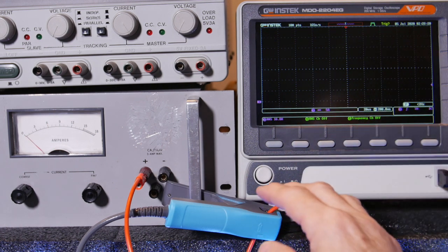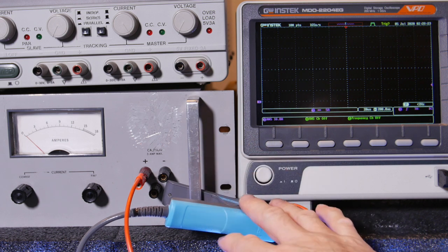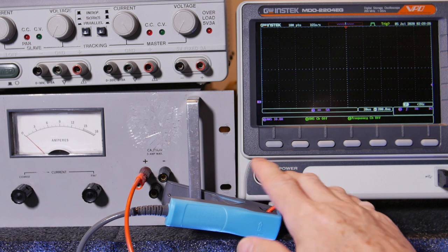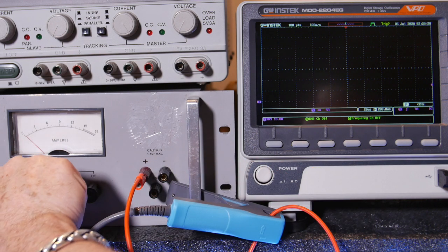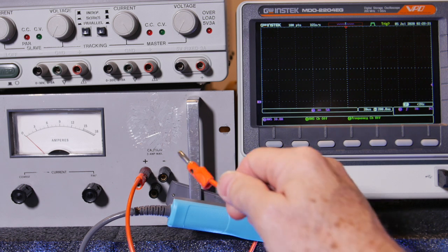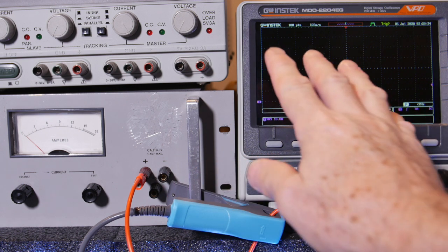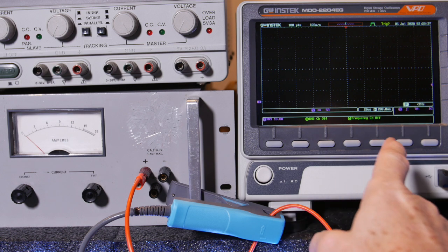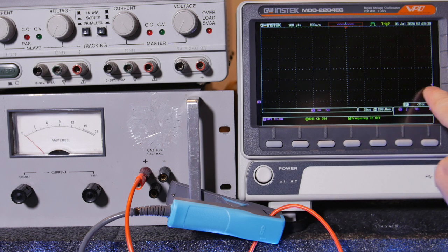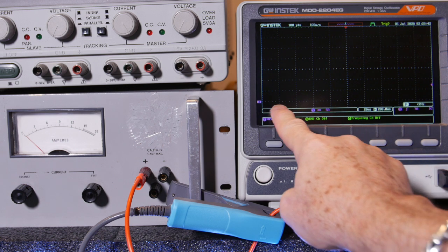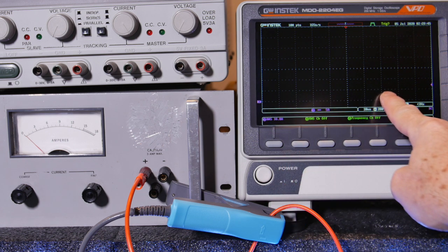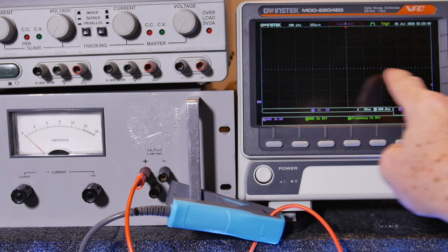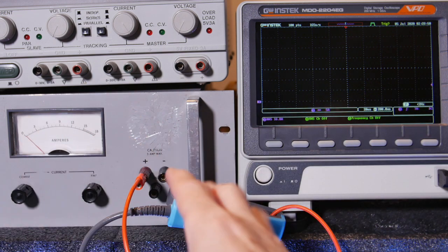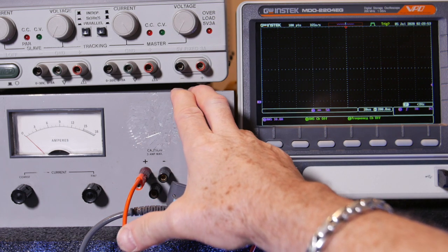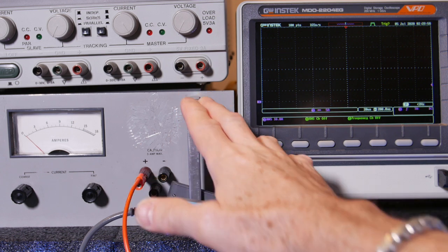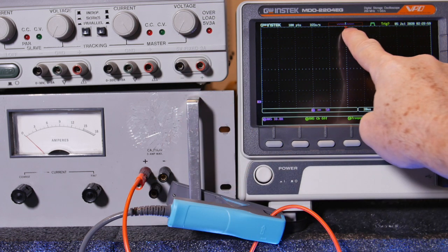Alright, we're going to go to a low current setting in a moment. But while we're set up on our 100 amp scale, let's try a surge current, okay? So what I'm doing is I've maxed this guy out, and we're going to just poke this in here. But what I have to do is go over to my scope and hit single trigger, okay? And then I'm going to see my triggers right here. By the way, I went to 5 amps per division. So 5 amps, so my trigger is set just above that. We should get at least 15, 18 amps. But you know what? There's some caps in here, and it'll be interesting to see how much surge current we get, okay? So it's going to trigger right here in the center.